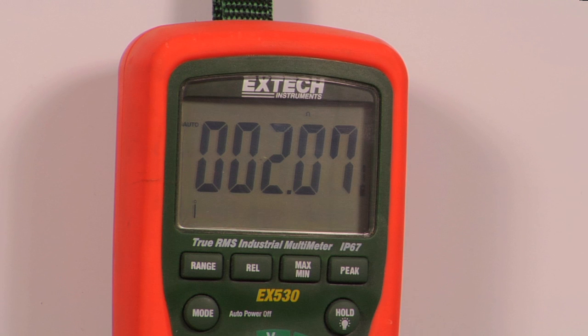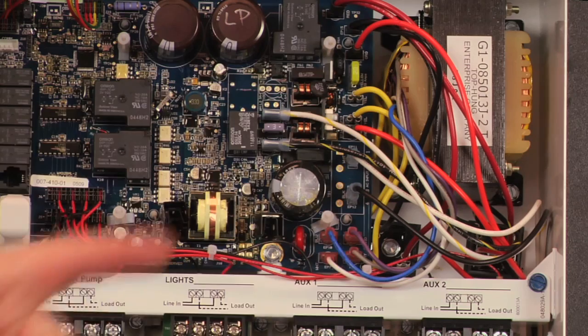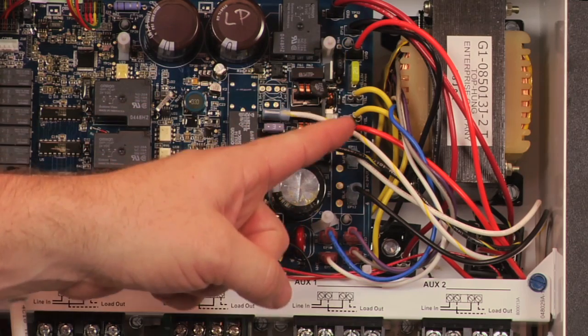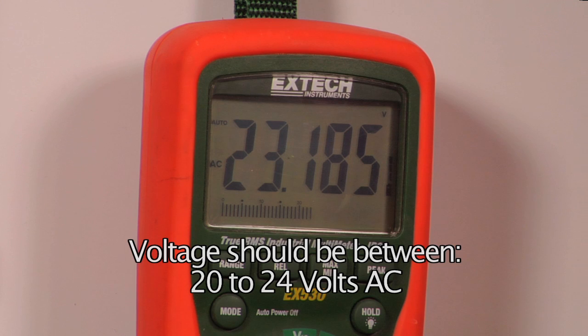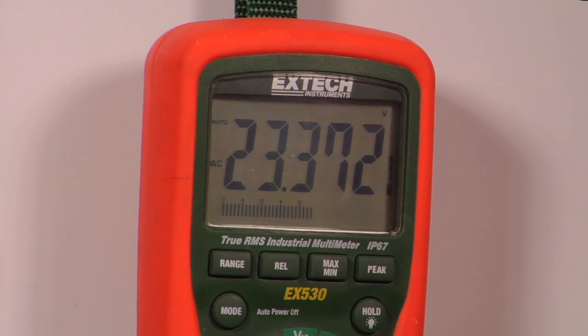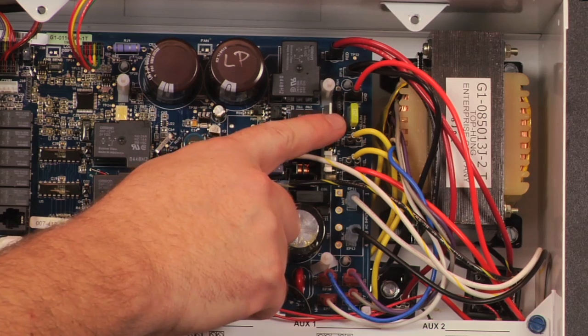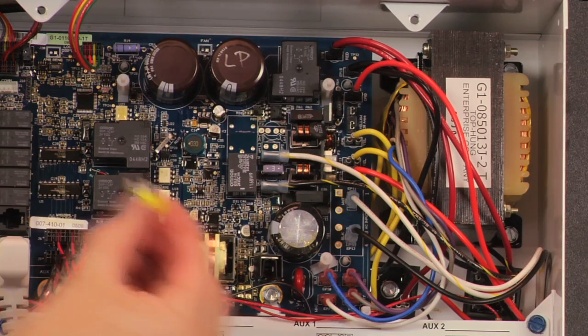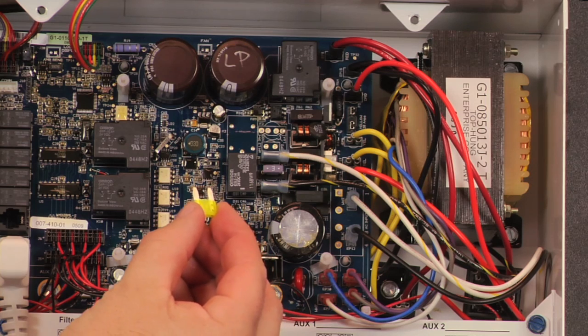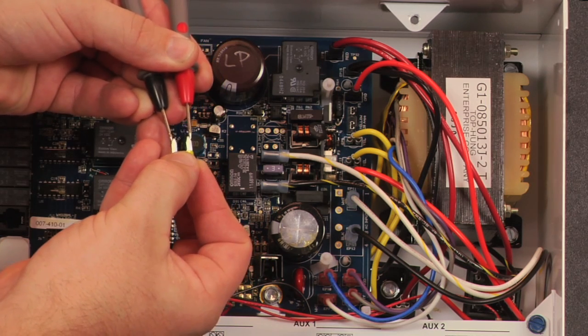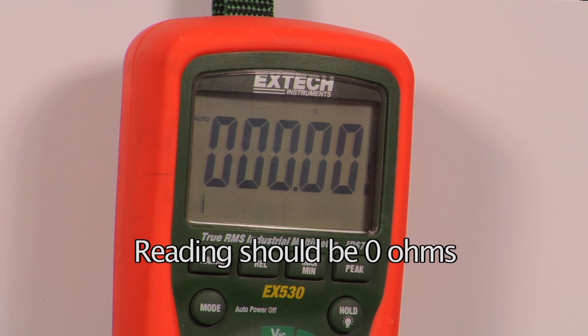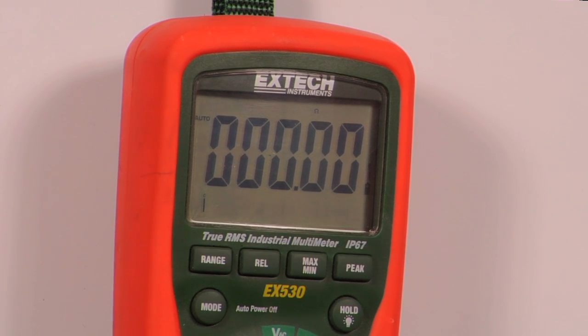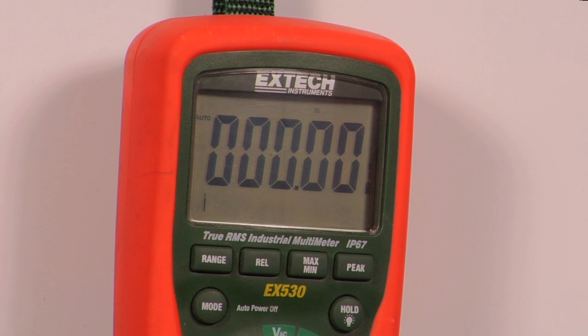If the voltage between the yellow terminals is good, measure the voltage between the orange terminals on the main board. The voltage should be 20 to 24 volts AC. If the voltage is not present, remove the 20 amp fuse from the main board. Measure the continuity of the fuse. The reading should be 0 ohms. If the fuse measures open, the fuse is bad and should be replaced.